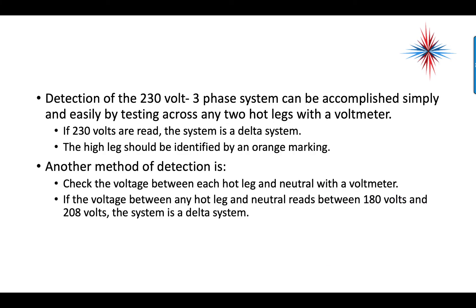Detection of the 230-volt three-phase system can be accomplished by testing across any two hot legs with a voltmeter. If 230 volts are read, the system is a delta system. The high leg, or longer leg, should always be identified by an orange marking. Another method of detection is to check the voltage between each hot leg and neutral — if any reading falls between 180 and 208 volts, the system is a delta system.